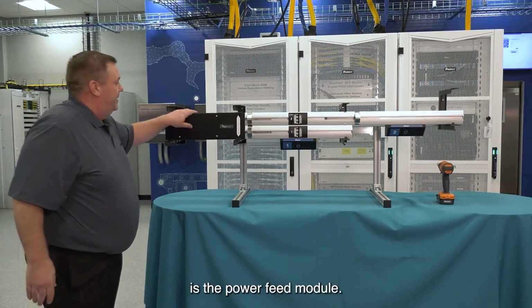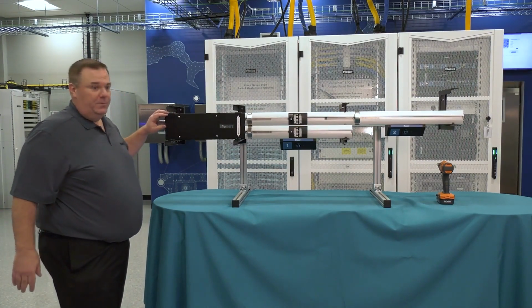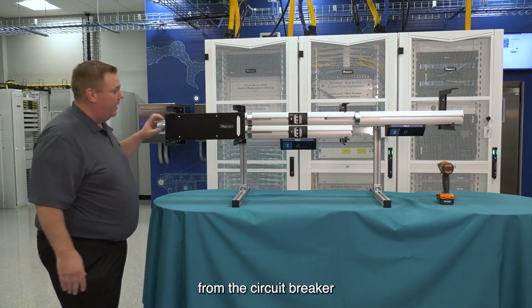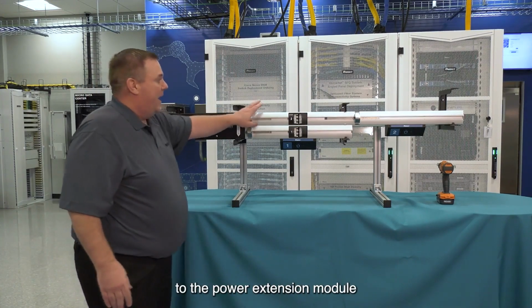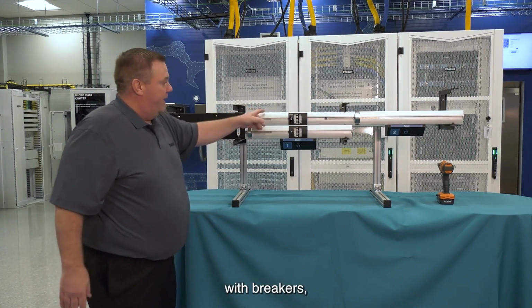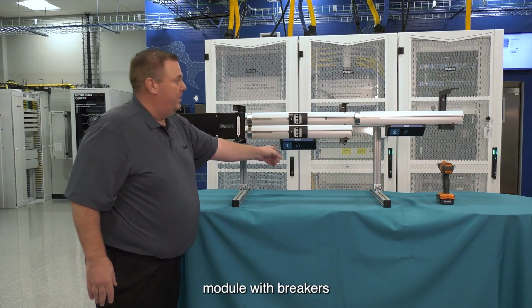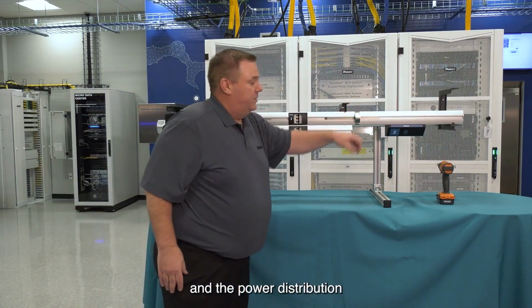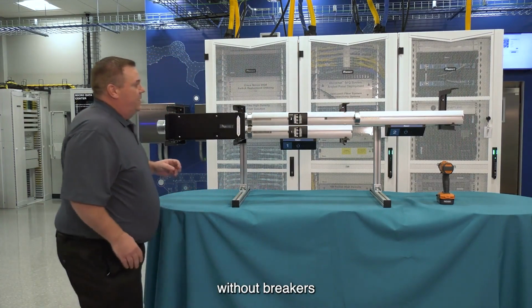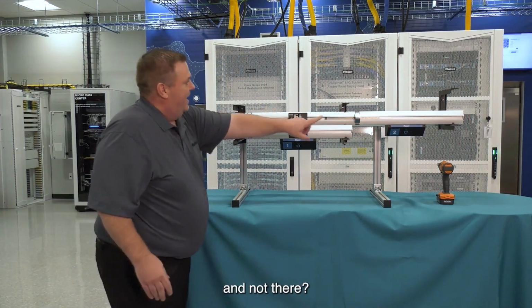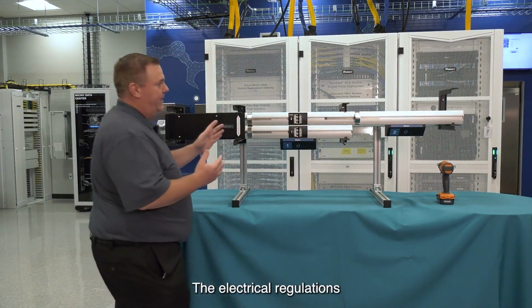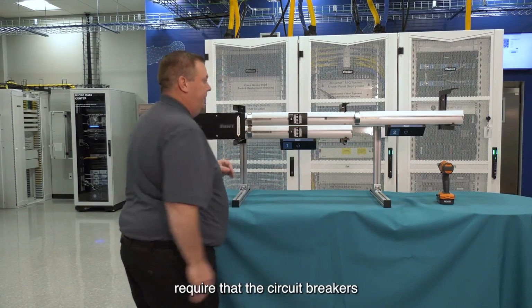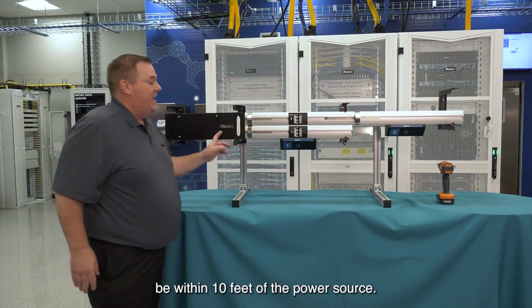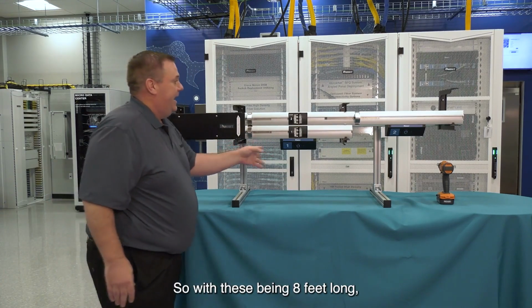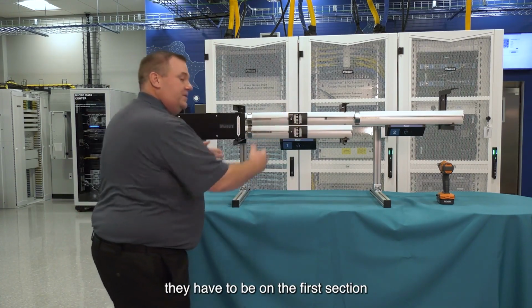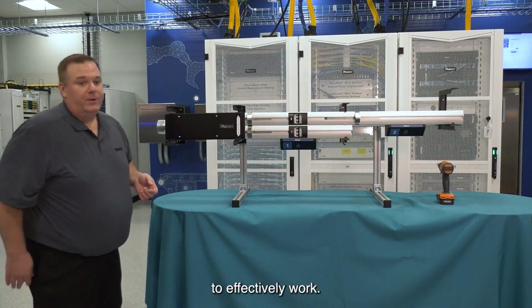This here is the power feed module. This is where the power comes in from the circuit breaker and then is distributed to the power extension module with breakers, the power distribution module with breakers, and the power distribution module without breakers. You might say, why are the circuit breakers here and not there? Electrical regulations require that the circuit breakers be within 10 feet of the power source. So with these being 8 feet long, they have to be on the first section to effectively work.